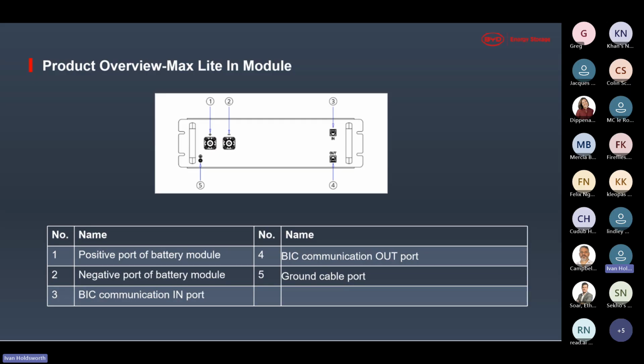So there's the earth point on the left, number 5, and you have your battery inputs and your BIC, battery information collectors, on your in and your out. The battery information collectors on the right, where it says in and out there, the BIC is behind that. It does your cell voltages, your cell voltage measurements, your temperature measurements, and your cell balancing.